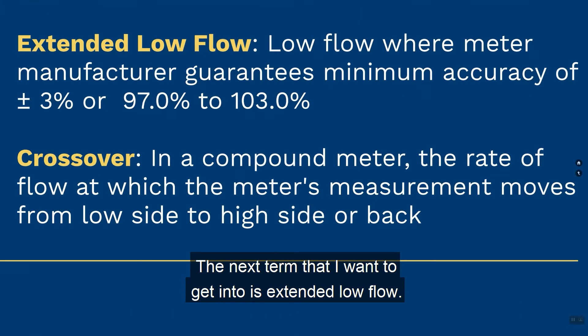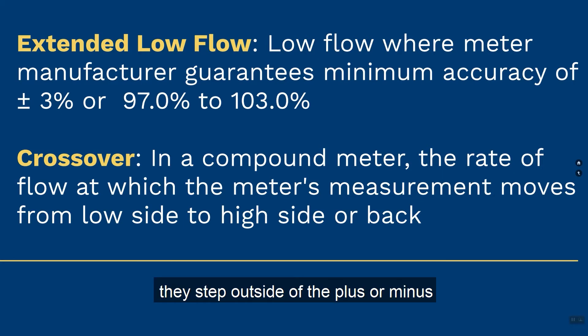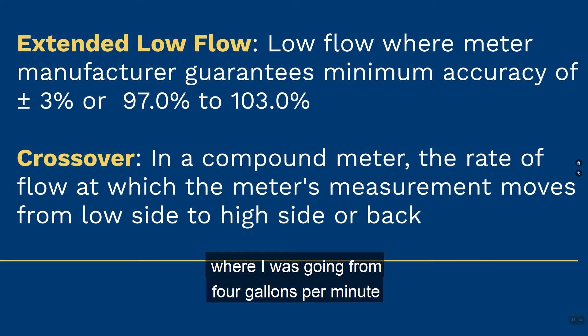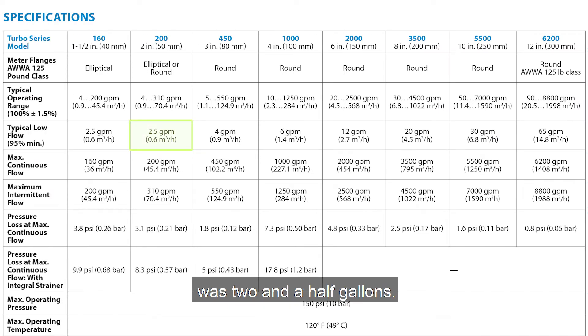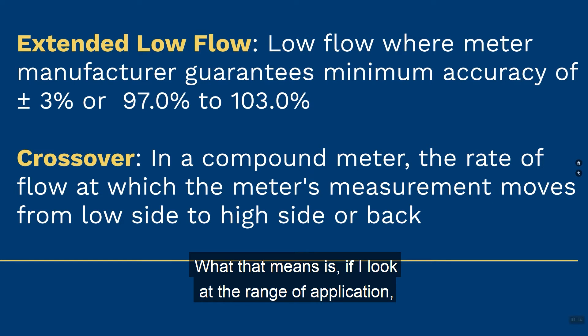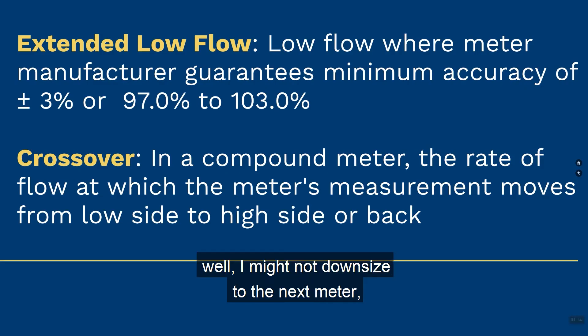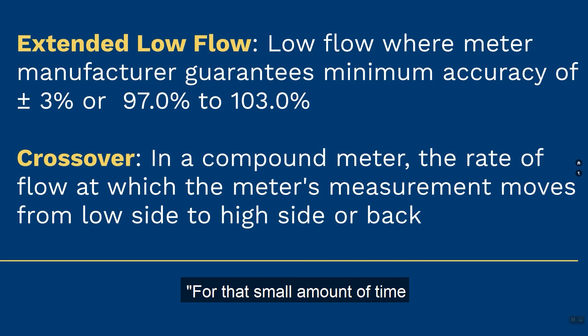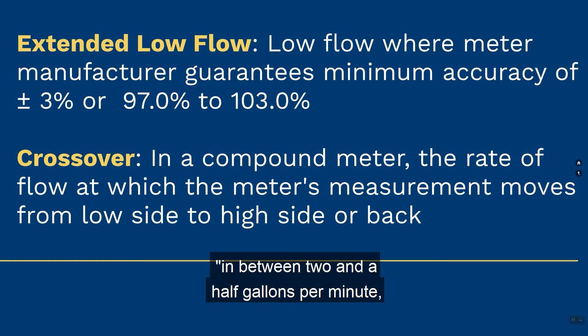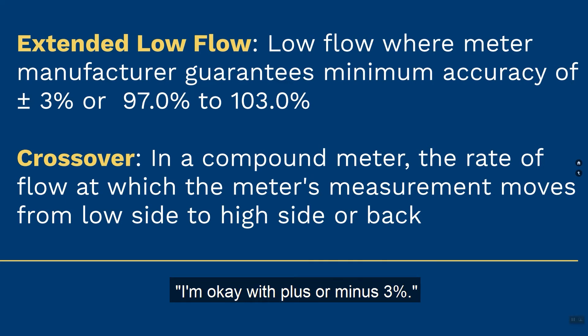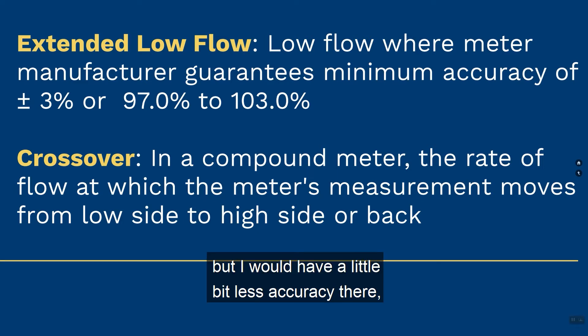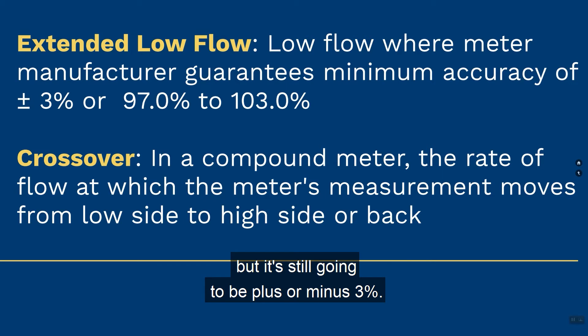The next term is extended low flow. This is a number that manufacturers provide stepping outside of the plus or minus one and a half percent guarantee. For example, if a meter's operating range is four gallons per minute up to 310 gallons per minute, and the extended low flow is two and a half gallons per minute, that means if the customer occasionally flows between two and a half and four gallons per minute, I might not downsize to the next meter. I'd look at the extended low flow and accept plus or minus 3% accuracy for that small amount of time.